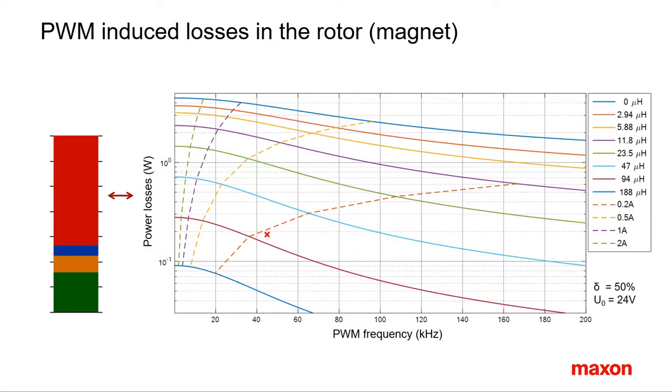Here the results of a simulation for the losses in the rotor, the magnet. It is for the red parts in the previous slide. The most important influence on these power losses stem from additional inductance. The higher the inductance, the lower the curve in the diagram, hence the smaller the losses. Observe the logarithmic scale on the vertical power axis. All curves show, the higher the PWM frequency, the more to the right in the diagram, the smaller the losses. We can conclude, higher PWM frequency and additional inductance help.